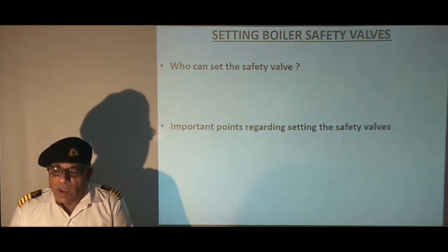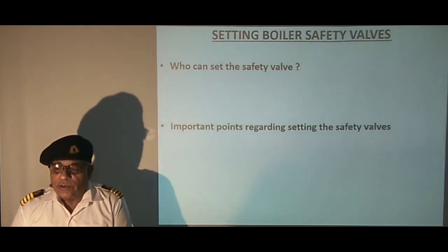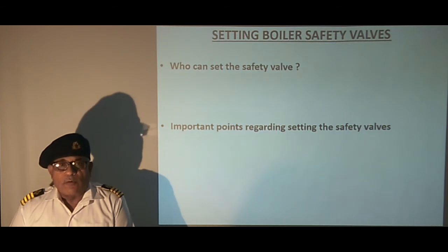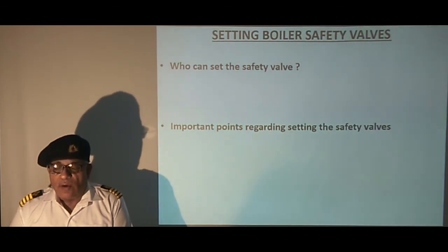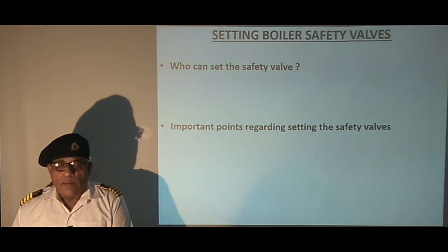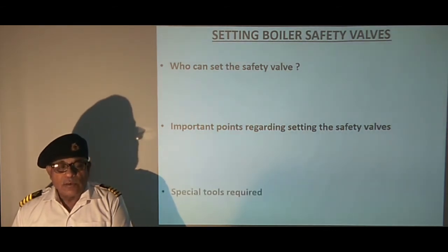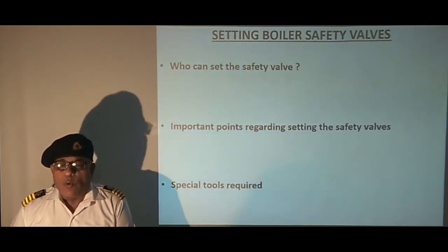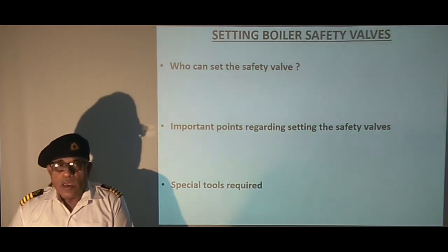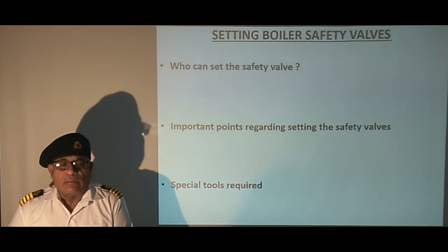For a new safety valve, pressure accumulation test should be carried out to confirm that the safety valve is of correct size. Coming to the last point, special tools are required. A gagging tool is required for isolating a safety valve. In the subsequent slide, we will see how the gagging tool looks.